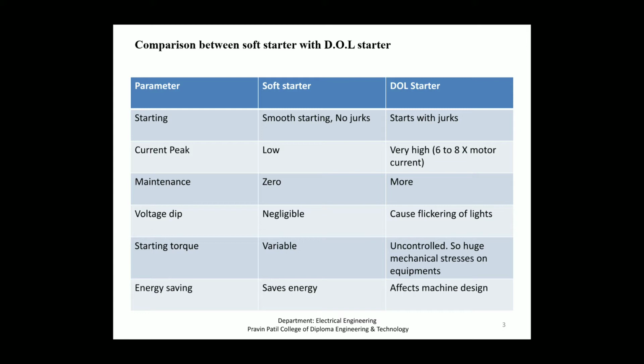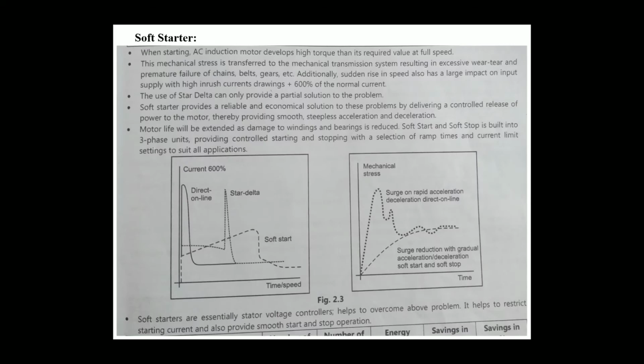Soft starter saves energy, but DOL starter affects machine design and creates maximum maintenance. Next, soft starter. When starting, an AC induction motor develops higher torque than its required value at full speed. This mechanical stress is transferred to the mechanical transmission system, resulting in excessive wear and tear and premature failure of chains, belts, gears, etc. Additionally, the sudden rise in speed also has a large impact on the input supply, with high inrush current drawing plus 600% of the normal current.